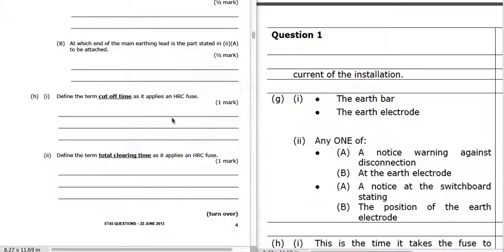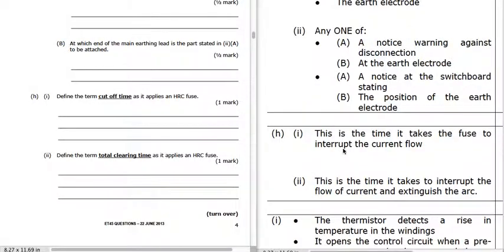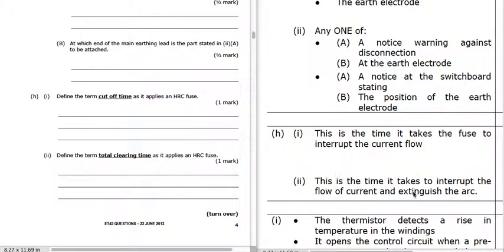Define the term cutoff time as it applies: the cutoff time is the time it takes the fuse to interrupt the current flow. The total clearing time is this time to interrupt plus the time it takes to extinguish the arc. So total time is the time it takes to interrupt the flow of current and extinguish the arc, whereas cutoff time is just when it interrupts the current flow.